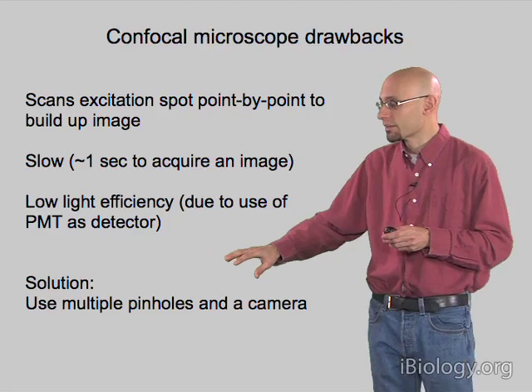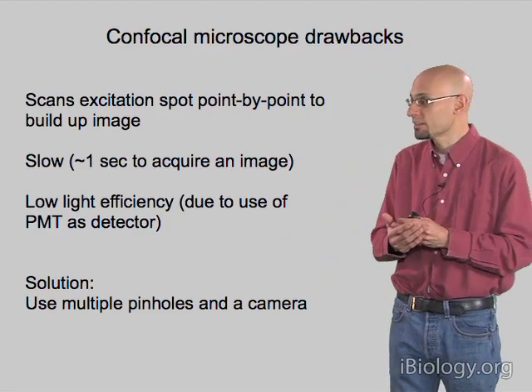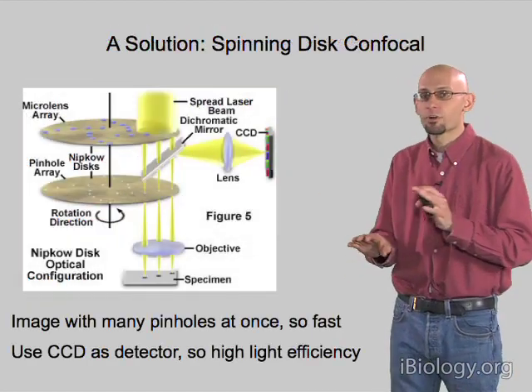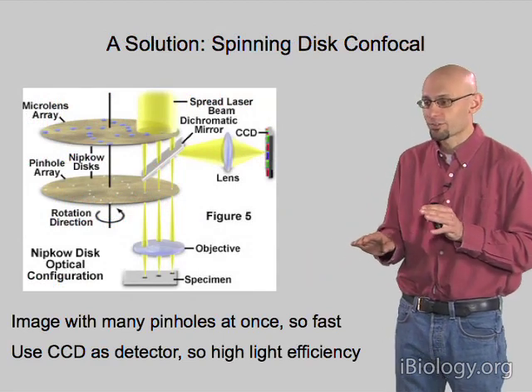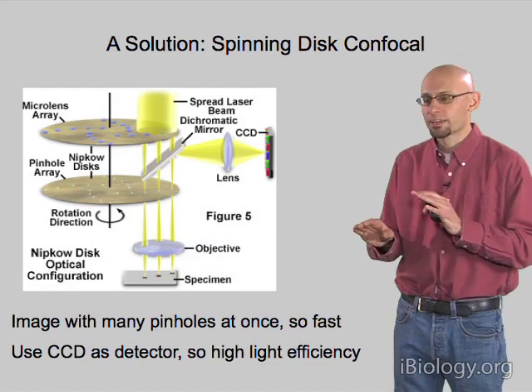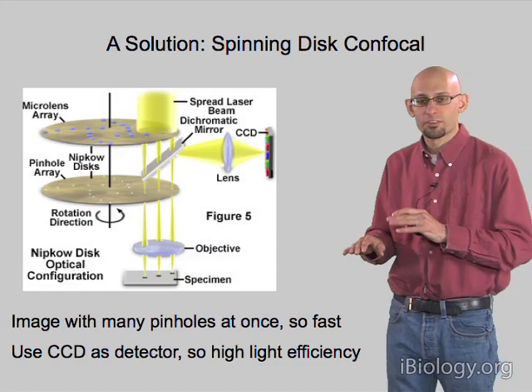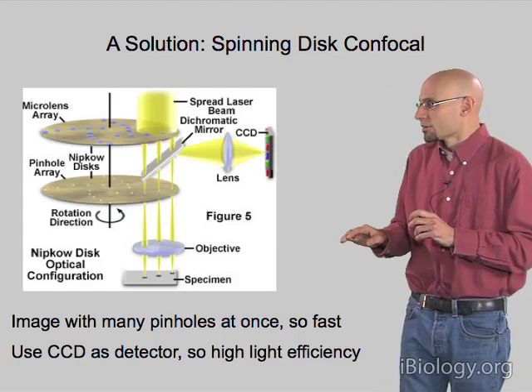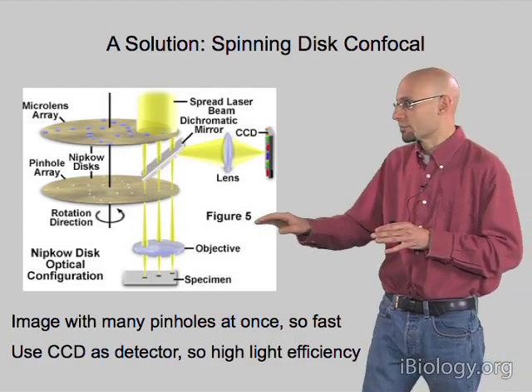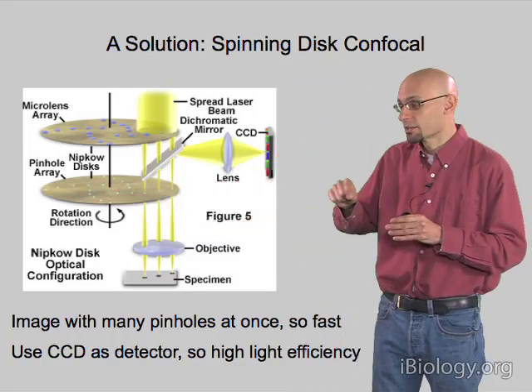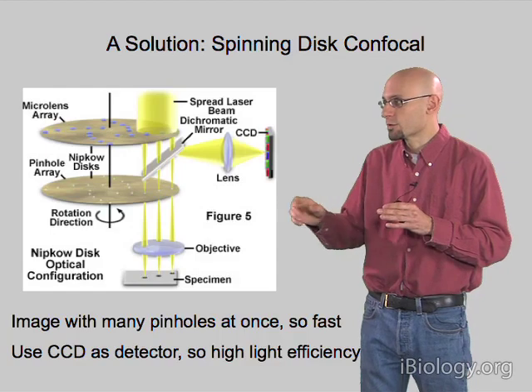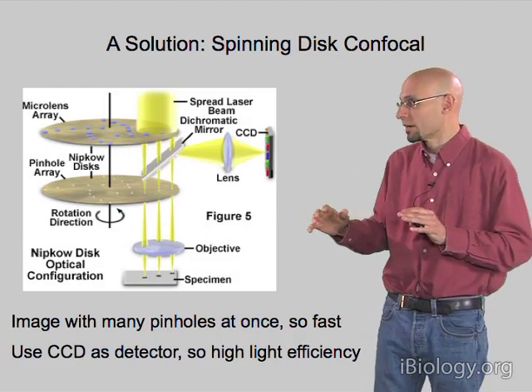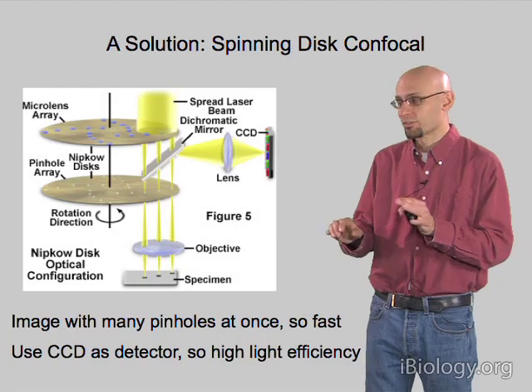Fortunately, there's a solution: instead of using a single pinhole and a PMT, we use many pinholes and a camera. This addresses both issues. The most common approach is called the spinning disk confocal. What a spinning disk confocal does is put a disk punched with many pinholes in it, arranged in a pattern such that if we rotate the disk around its axis, those pinholes will sweep out across every point in our sample once and only once — so for every rotation, we illuminate every point exactly once.